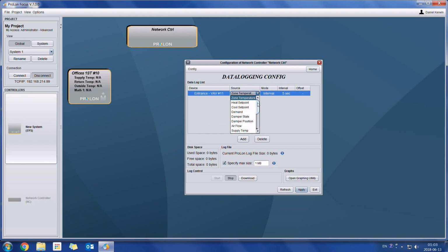I can double click on the source. So here we have a list of all of the points of that controller. In this case I would want to log the zone temperature, and I can choose what is the interval. In this case we have 5 seconds, but we probably don't want 5 seconds. That might be a bit too fast, so I could put it to 1 minute. So now every minute it's going to log the space temperature.